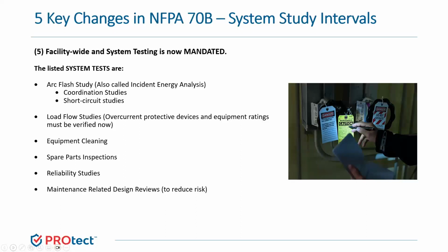Please note that 5 years is the maximum period between tests, but there are now specifically listed events which would require each of these system tests to be performed or updated. For example, installing new electrical equipment might warrant that you do some of these tests or updates before you meet that 5 year compliance cycle, just to make sure your one-lines are up to date as you make changes to your systems.